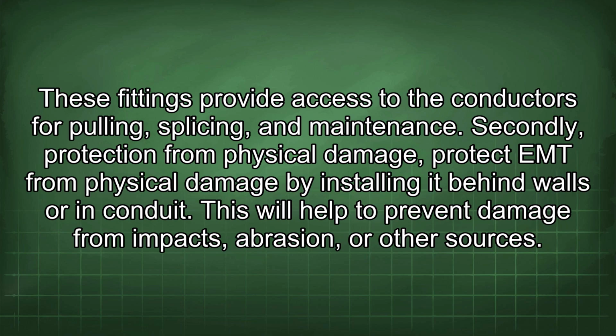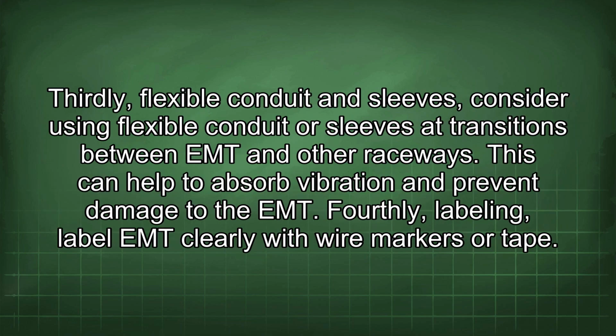Secondly, protection from physical damage. Protect EMT from physical damage by installing it behind walls or in conduit. This will help to prevent damage from impacts, abrasion, or other sources. Thirdly, flexible conduit and sleeves. Consider using flexible conduit or sleeves at transitions between EMT and other raceways. This can help to absorb vibration and prevent damage to the EMT.